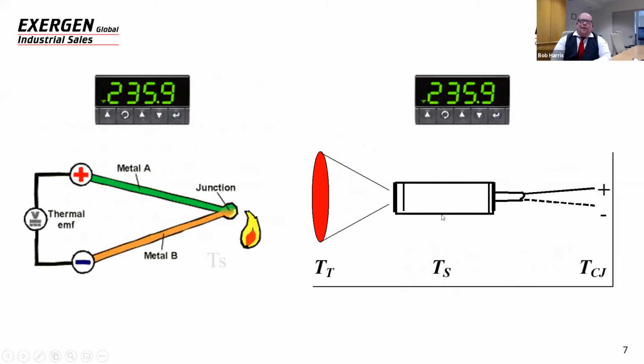So here's an example. On the left, we have a conventional thermocouple. As you can see, the conventional thermocouple measures the temperature at the junction, and we have a little display there that's displaying the temperature of that surface. The IRTC on the right is aimed at that same surface and is calibrated at around 240 degrees, it looks like here, so that it can measure the same temperature that the conventional thermocouple does, in the same readout device.